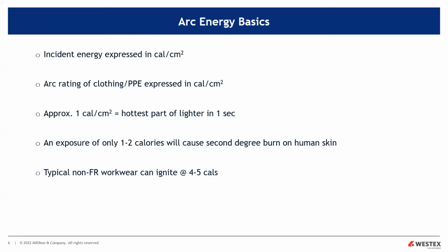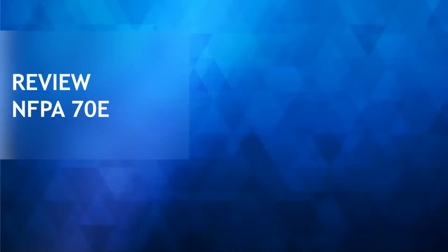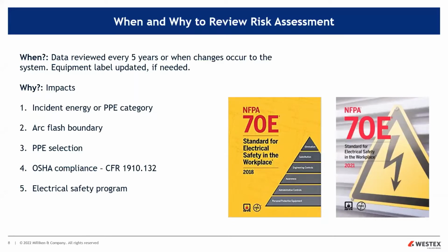That's going to cause a second degree burn on exposed skin. And of course, non-typical workwear can ignite as low as 4 to 5 cals. Your lightweight shirts, your t-shirts certainly will ignite at 4 to 5 cals. If you're just wearing regular blue jeans, that's going to take a little more energy, 8, 9, 10 cals, because they're thicker. But you get the picture. Let's review NFPA 70E and why we need to look at the reassessment. Every 5 years, you have to do that regardless, or when changes occur to the system. And then of course you need to make sure and verify that the labels on your equipment are updated.